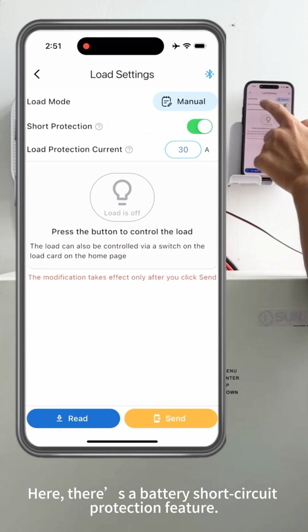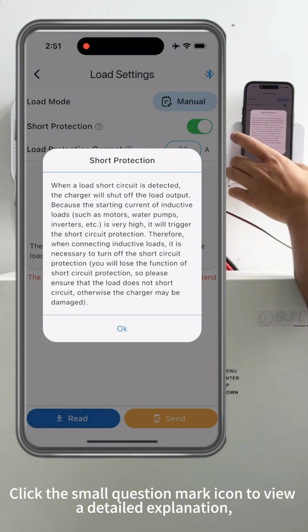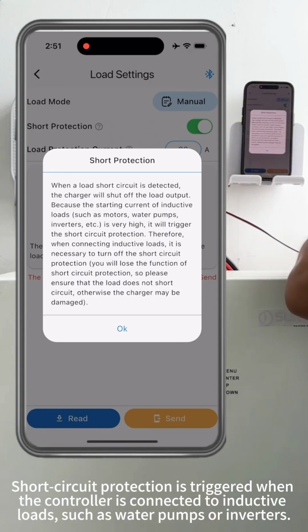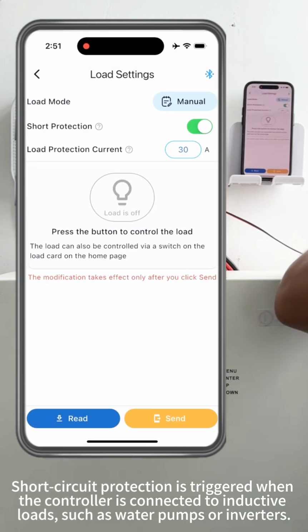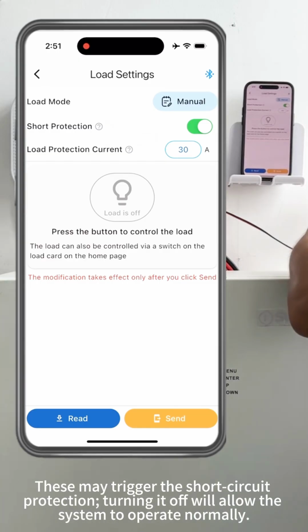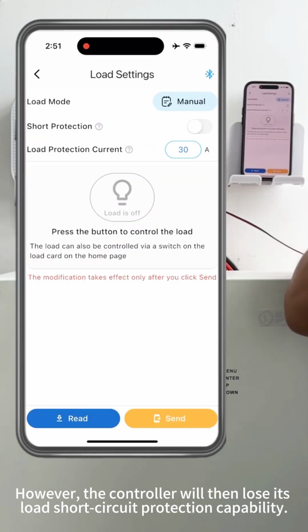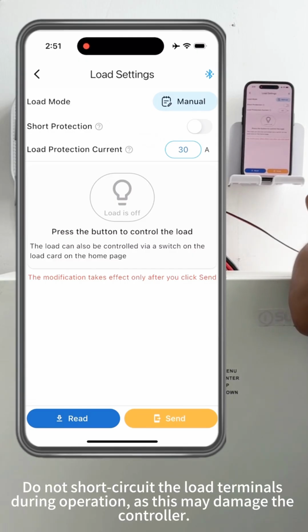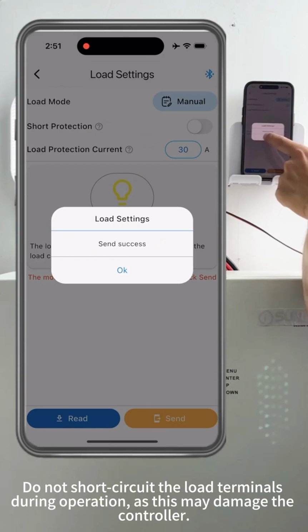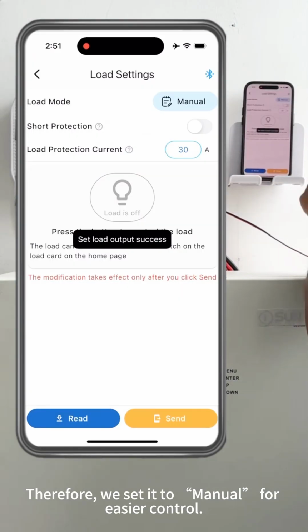Here, there is a battery short circuit protection feature. Click the small question mark icon to view a detailed explanation, which helps us understand and troubleshoot issues. Short circuit protection is triggered when the controller is connected to inductive loads, such as water pumps or inverters. This may trigger the short circuit protection. Turning it off will allow the system to operate normally. However, the controller will then lose its load short circuit protection capability. Do not short circuit the load terminals during operation, as this may damage the controller. Therefore, we set it to manual for easier control.